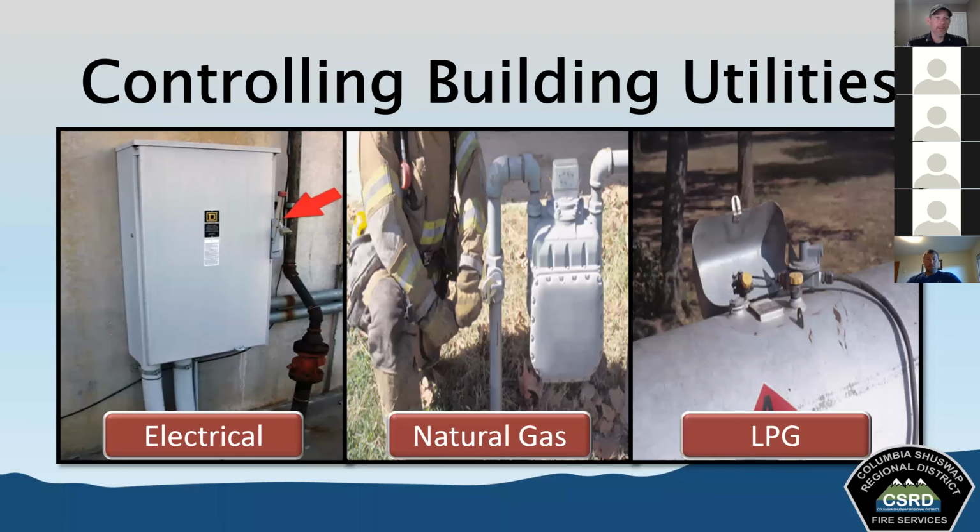It's used as well as a fuel for motor vehicles. Like natural gas, it has no odor, but they add a smell to it so that we know when there's a leak. Again, non-toxic, but classified as an asphyxiant, will displace oxygen and we won't be able to breathe. With propane, a little different than natural gas is that it's 1.5 times as heavy as air, so it's about 50% heavier than air.